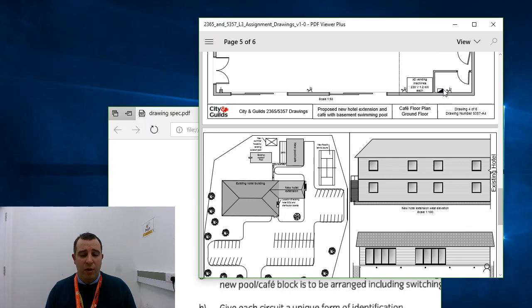I mean, you can add more and more things off there. I would expect this board would be sort of an 18-way three-phase, so it'd have best part of 54 different ways within that fuse board. And don't panic that you've only used about 10 or 12 of them, because what you've got to consider is that there is a lot more other stuff that would be added in, and you'll probably need to add them on as you go later in there.